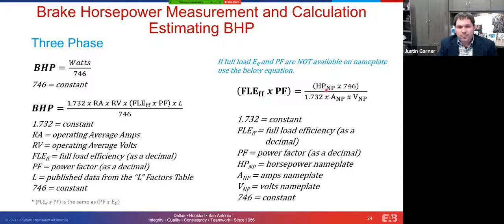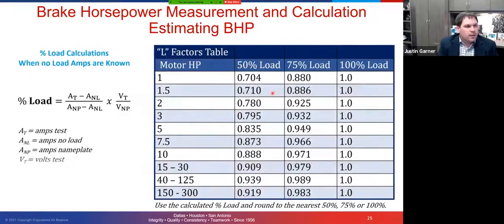You take your nameplate horsepower times 746. We're converting it back to watts there. And then we divide it by our 1.732 times our nameplate amperage times our nameplate voltage. And this is going to give us our nameplate value for this, which is what we need for this calculation. Then the next component, we're going to need to estimate our percent loading.